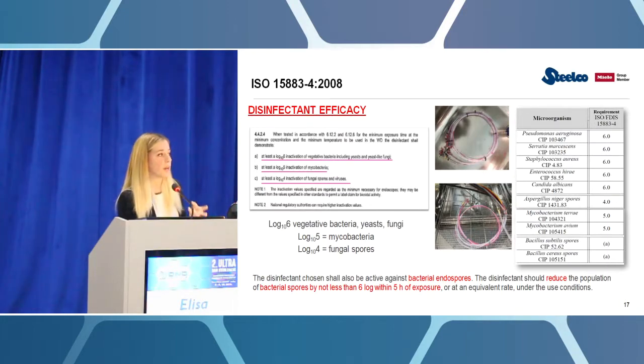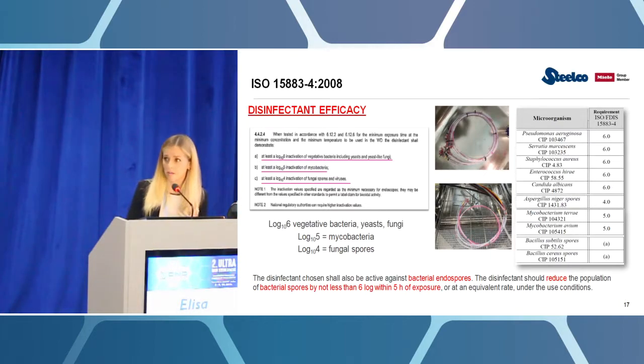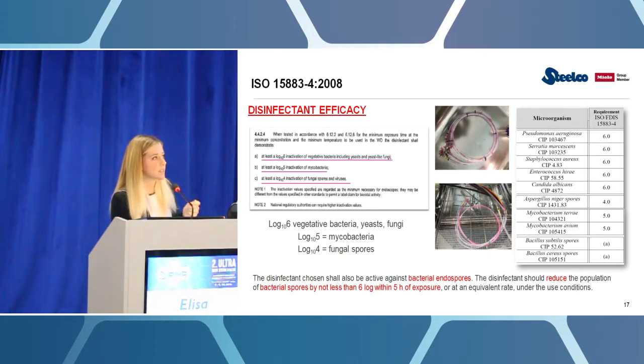This is why the 15883 standard requires endoscope washers to be closed systems. That means these machines must work only and exclusively with chemical substances validated by the manufacturer of the machine. We can't use whatever chemical we like, because we need to provide evidence that the chemical is doing all of these things.